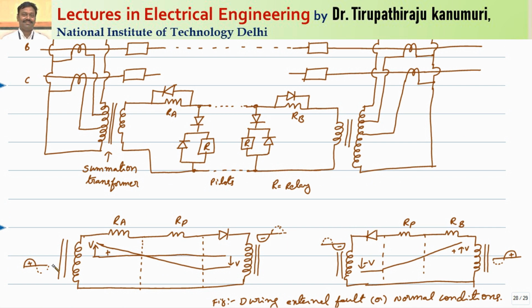Under normal operating conditions or through fault conditions, as they are connected in the current balance scheme, if the voltage on one side is positive, the voltage on the second side will be negative. That's why it is called a circulating current scheme. Whereas in the differential voltage or voltage balance scheme, if this is positive here, at the same instant it will be positive here also, and because the difference in voltage is equal to 0, no current is circulated. But in the circulating current scheme, if one side is positive, at the same time the second side will be negative. The connections are made in such a way.